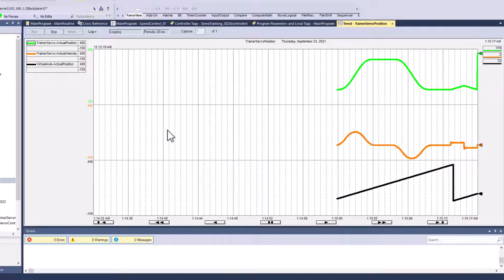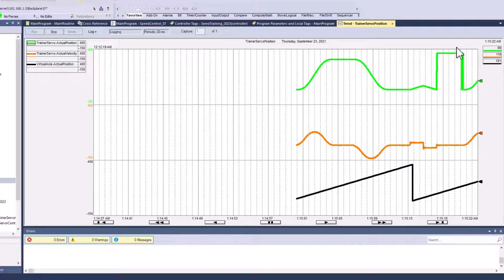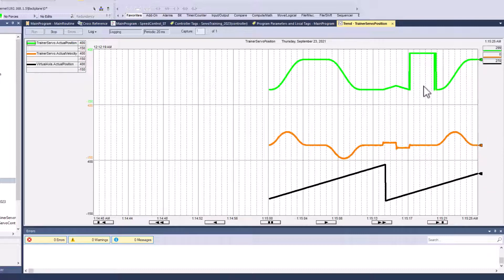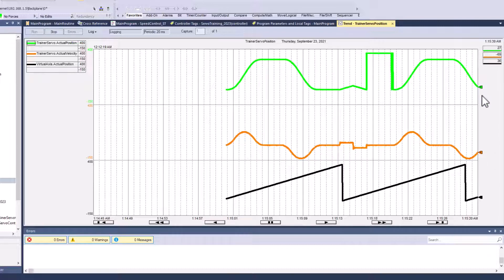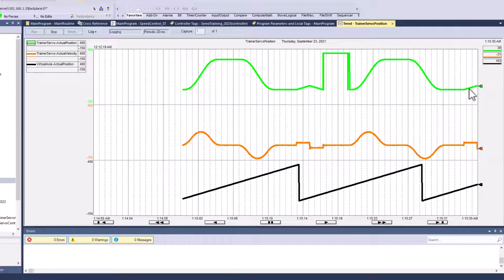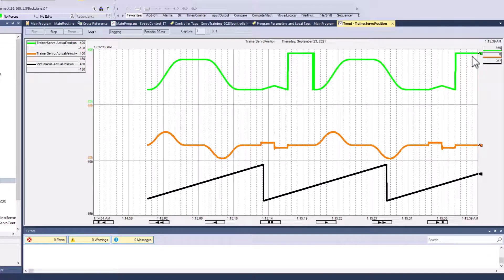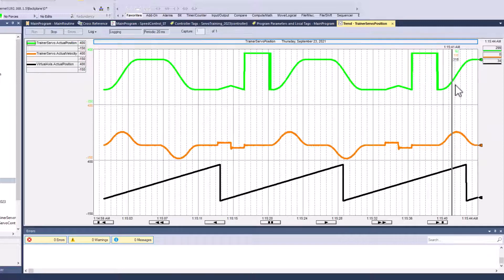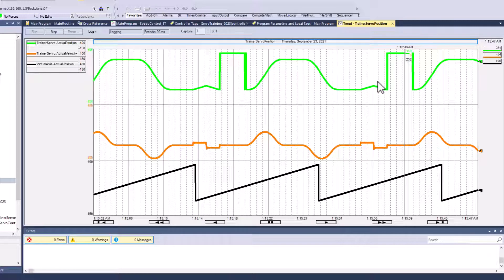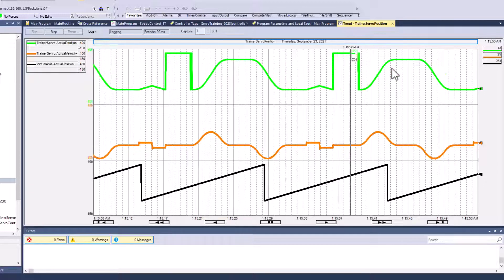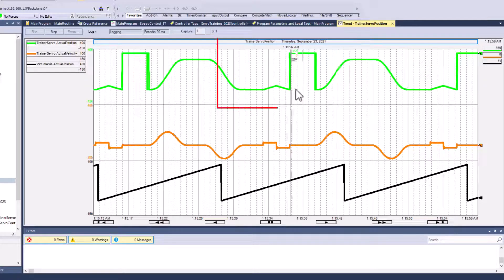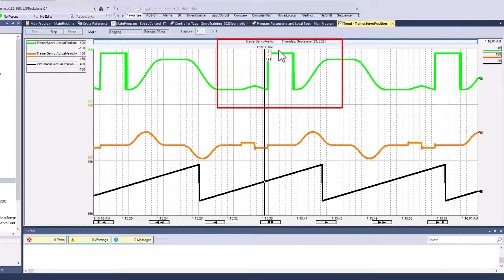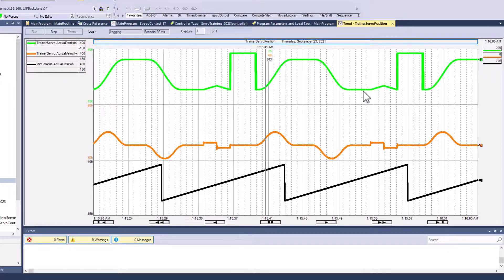And you will see, this is the cam. This is the velocity. The orange is the velocity. And you'll see right there that that is exactly what's happening right here. So you see, I have my first move to 300, my second move to zero. And then this little blip right here is the cam. And then what it does right here is turning off the way my logic is. I'm turning it off, so that's why it shoots up here. That's the only reason. Plus keep in mind the rollover, if the rollover is zero, like from zero to 360, you will occasionally see it bounce between 360 and zero. And that's what we're seeing right here. We're seeing a zero and then it's jumping to 360 and then bouncing back. That's all we're seeing.